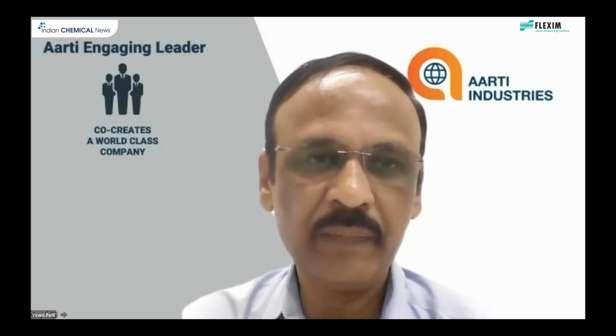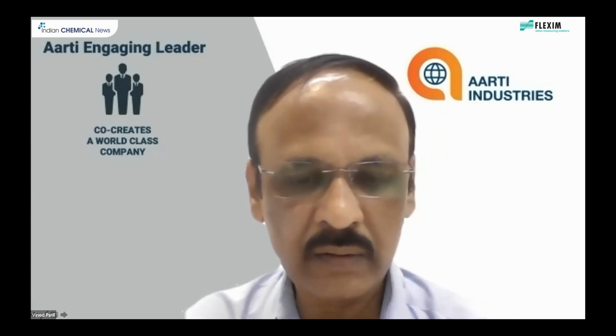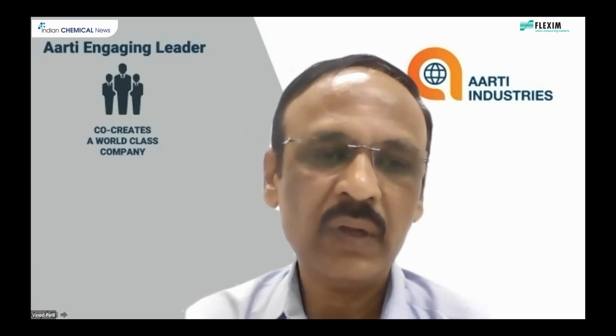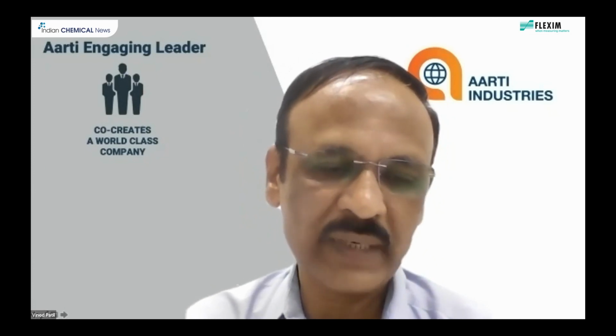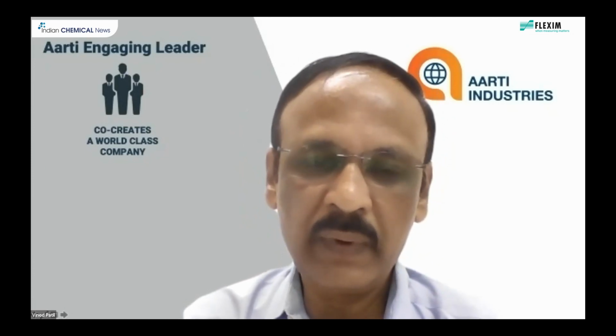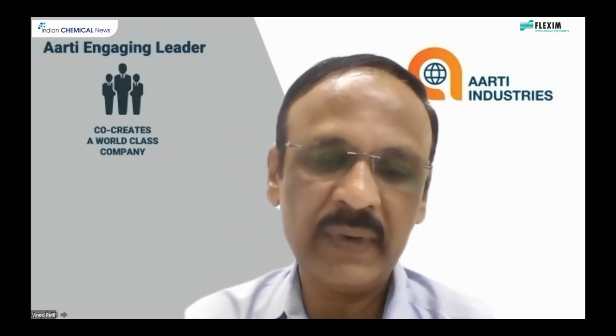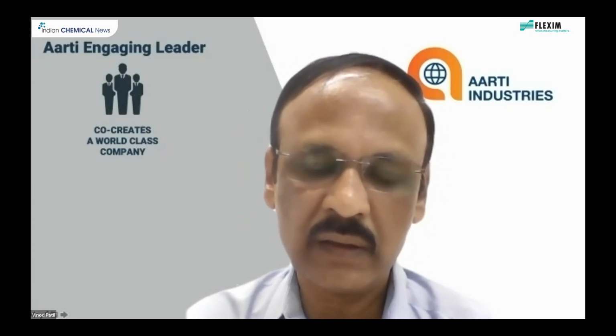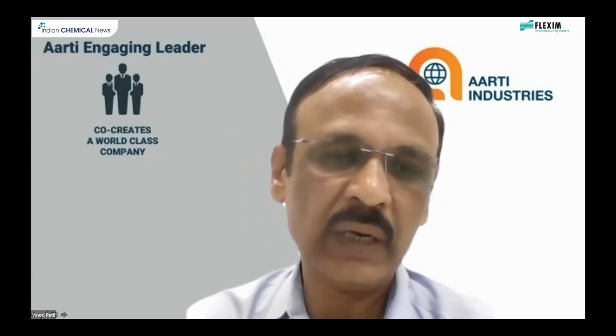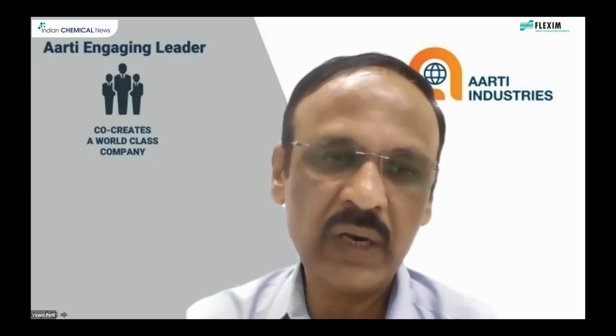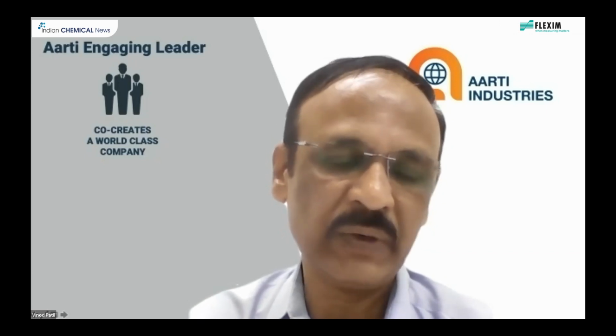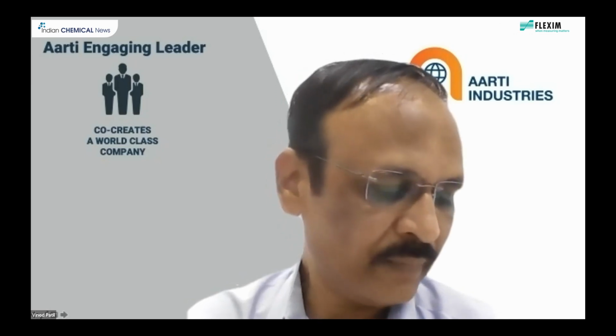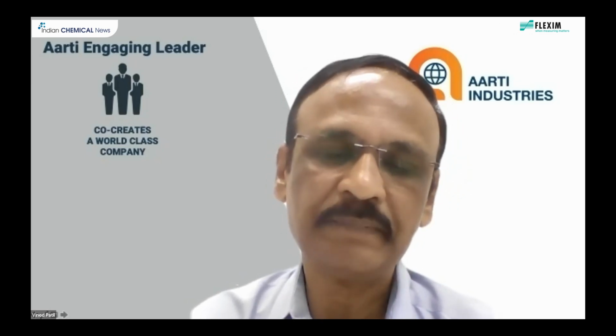And the second is a portable type, which we are utilizing for verification of the process parameters. It is used to enhance our processes for online measurement. Through the portable, we are verifying the exact process parameters and analyzing where the process has deviated, using that portable clamp-on flow meter. We are also utilizing the same flow meter for energy conservation, for the measurement of cooling water and pump discharges, where we got a lot of benefit from these flow meters. Yeah, Prashant. And are you happy? And is it serving your purpose, sir?